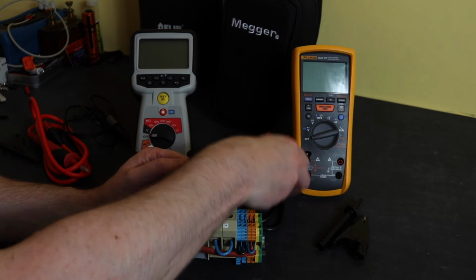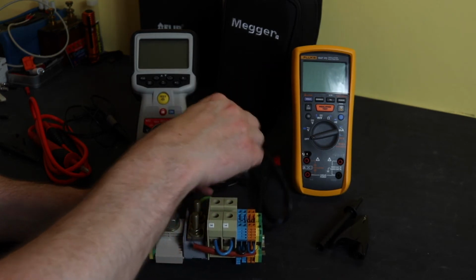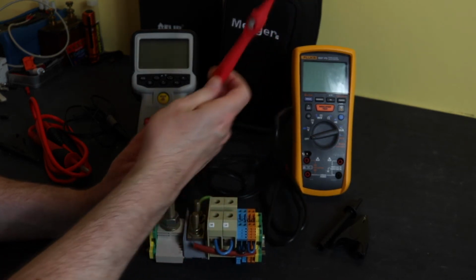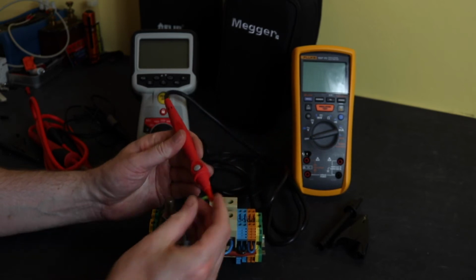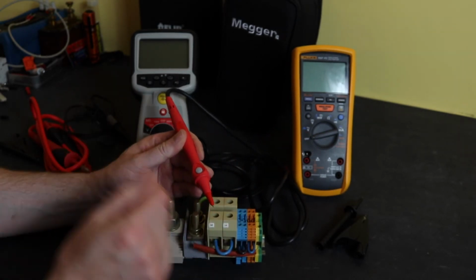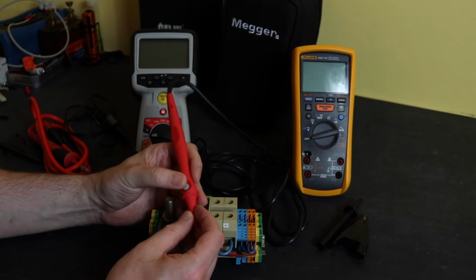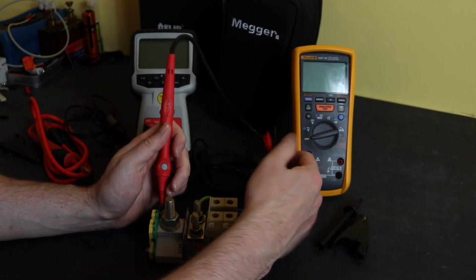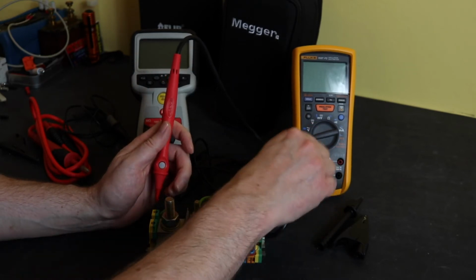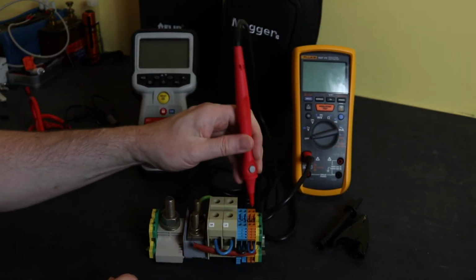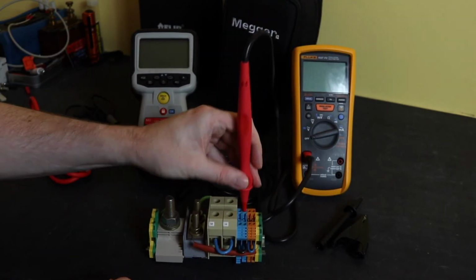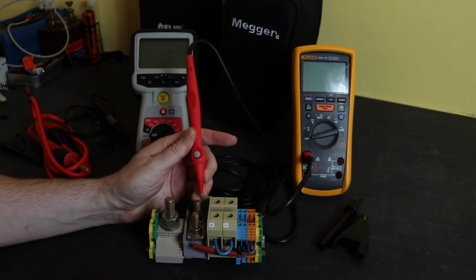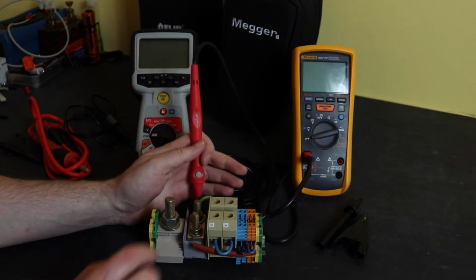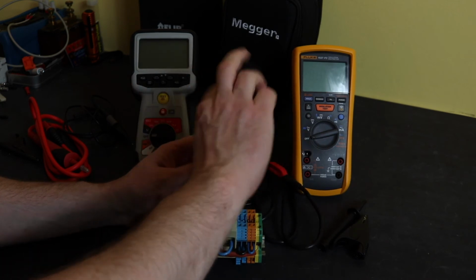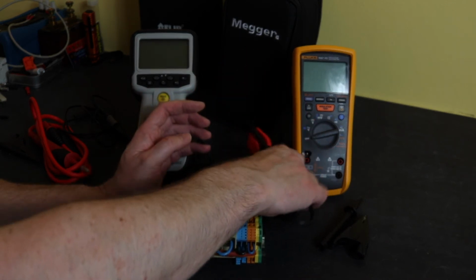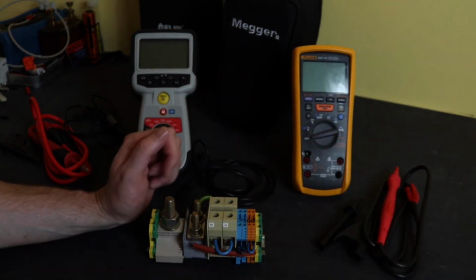It's those two. The remote probes, again, they have removable GS38 caps, they both have that, and you can operate the instrument from them. If you're going along a terminal rail, you can keep going along and pressing the button and taking a number of tests in quick succession. That's the only thing that I would use that kind of thing for, probably more in a distribution board, going along.